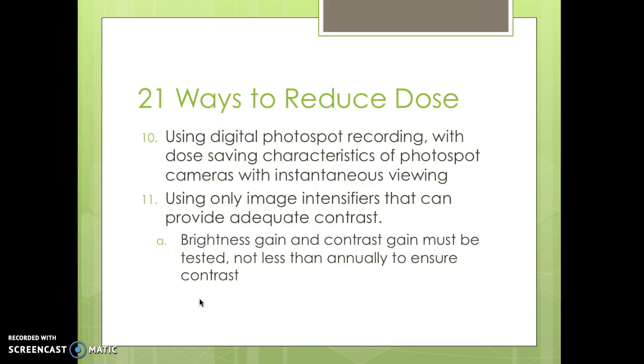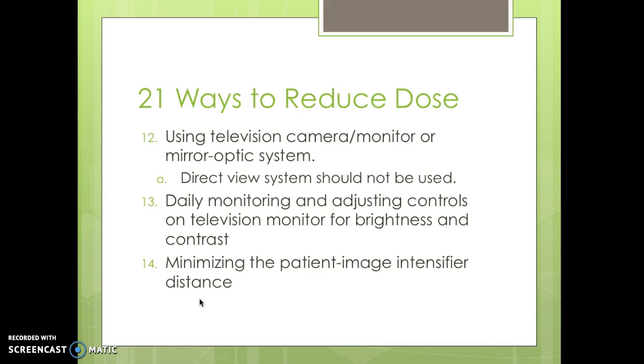Use digital photo spot recording with dose-saving characteristics of photo spot cameras with instantaneous viewing. Use only image intensifiers that can provide adequate contrast — brightness gain and contrast gain must be tested not less than annually. Use television camera monitors or mirror optic systems; direct viewing systems should not be used. Daily monitoring and adjusting controls on the television monitor for brightness and contrast is also required.